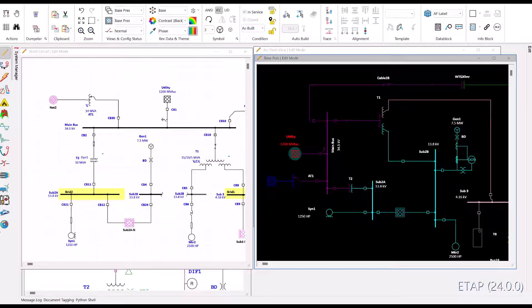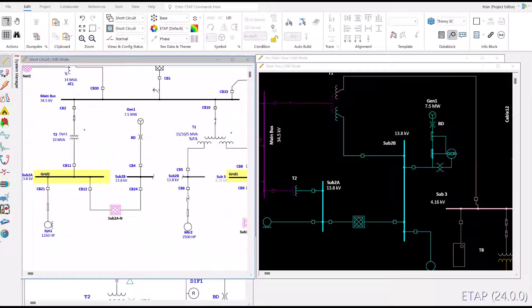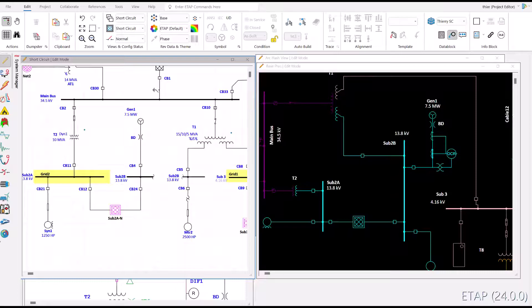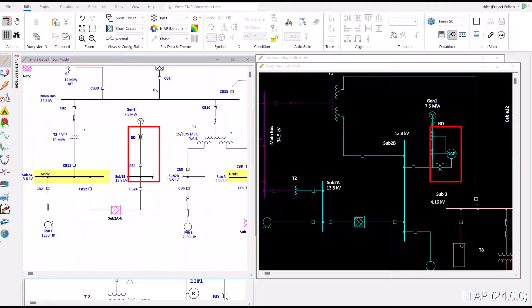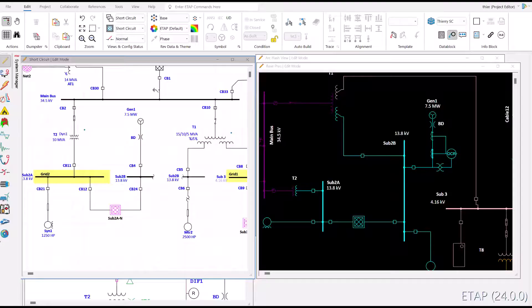Another layer difference: look at sub 2B. In the base presentation, there is a relay OCR around Gen 1. In the short circuit studies view, there is no relay OCR around Gen 1. I hide the relay. You can do that in any ETAP presentation without changing the original base presentation. Why did I hide OCR in the short circuit view? Relays have no impact on short circuit studies. To simplify the layout for my audience, I hide the relay in this view. We will only focus on components that matter during short circuit studies.